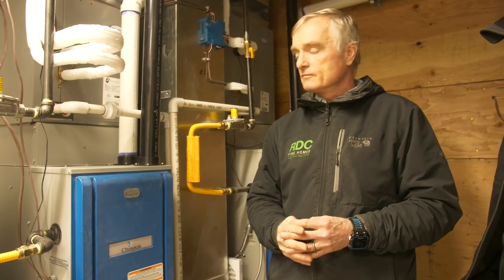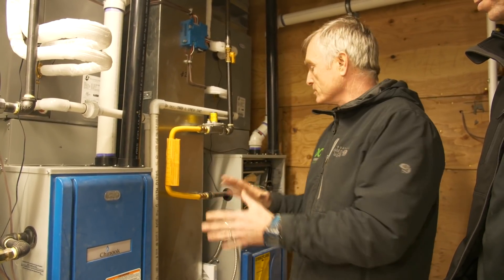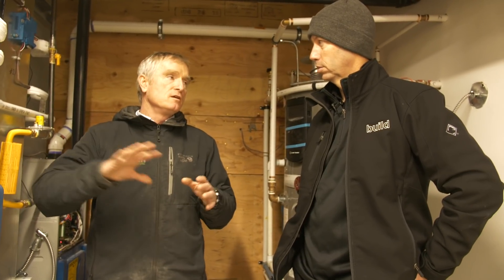We did heat loss calculations room by room for the entire house to make sure we had right-sized equipment, and this whole setup was designed by Dettson based on those heat loss calculations from our energy model. HOT2000 is the model we use in Canada — similar to a HERS rating in the United States — and it gives us calculations we can use to not only size our furnaces but to engineer our duct runs and duct sizing.